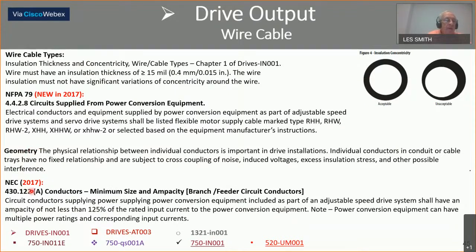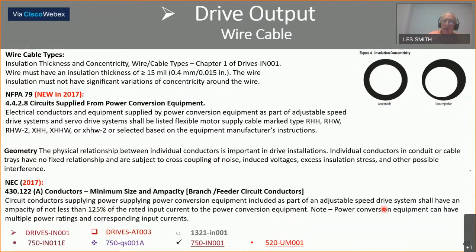NEC 430.122 requires 125% of rated input current for wire sizing. Drives are dual-rated now: for example, you can have a 75 horsepower drive or a 60 horsepower drive from the same unit, depending on whether it's heavy duty or normal duty. I'd recommend reading that on your own to stay up to date on minimum wire sizing specifications.